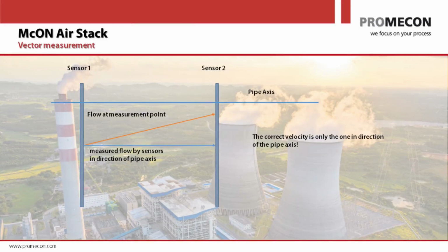And the distance is exactly the vector between the two sensors. And that's the whole thing. If the air, like you have the orange arrow here, that's the airflow, or maybe you have a swirl going through the two sensors. The sensors don't care. The sensor only measures two time events, and the system calculates with the distance vector between the two sensors that is perpendicular on the sensors. So any lateral air velocity will simply be ignored. The system does not measure lateral airflow. Whereas all other systems, the Venturis and the Pitots and all that, are affected by lateral airflow heavily.